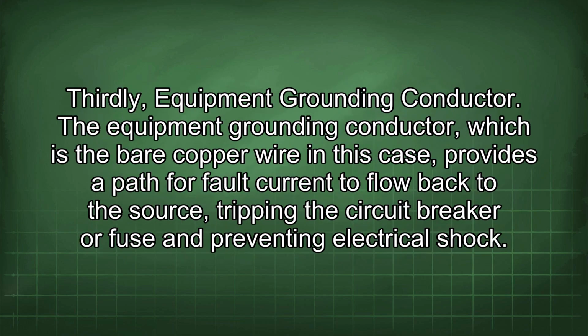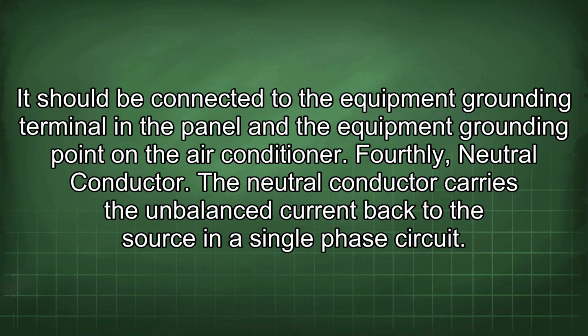Thirdly, equipment grounding conductor. The equipment grounding conductor, which is the bare copper wire in this case, provides a path for fault current to flow back to the source, tripping the circuit breaker or fuse and preventing electrical shock. It should be connected to the equipment grounding terminal in the panel and the equipment grounding point in the air conditioner.